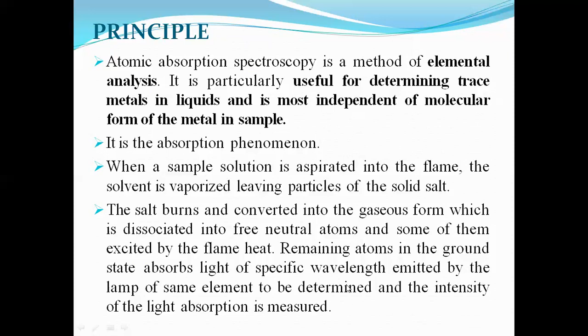So what happens in this technique? There is a light source, which is a radiation source, and we supply our sample through the flame. The flame temperature will vaporize the solvent which is used to dissolve our sample. Once the solvent is vaporized, the solid salt particles remain. This salt burns and is converted into gaseous form, which is dissociated into free neutral atoms by the flame temperature, and some of them go into the excited state, and the remaining atoms present in the ground state will absorb the light of specific wavelength passed from the radiation source. This light absorption is measured by the detector.